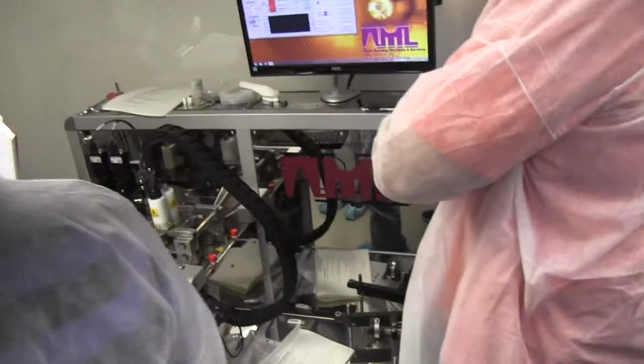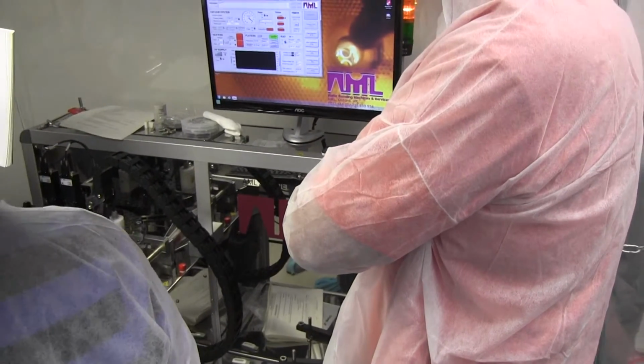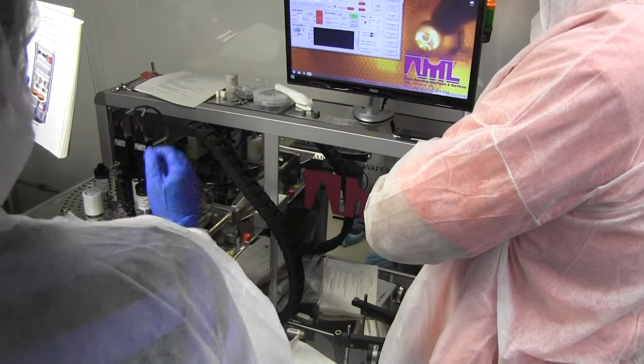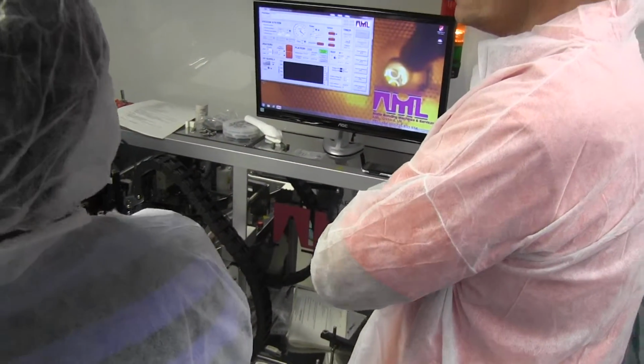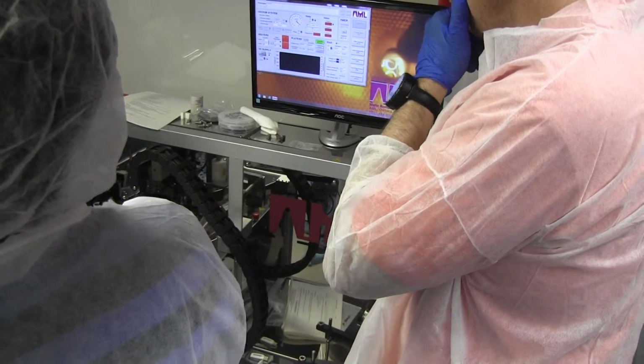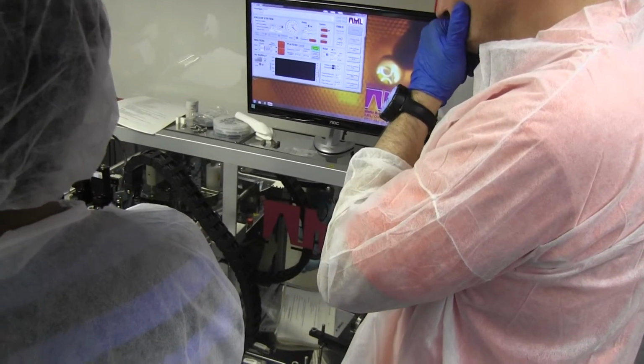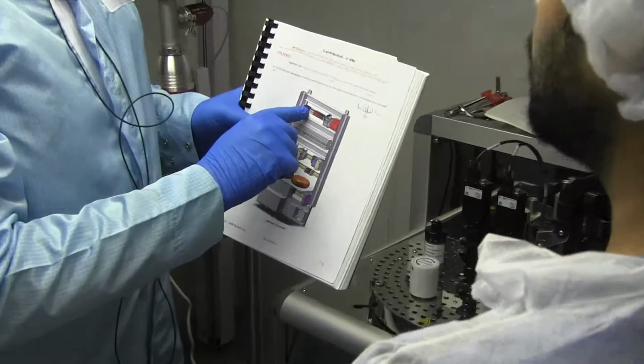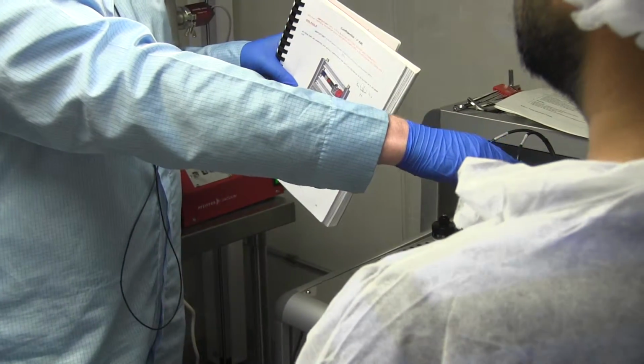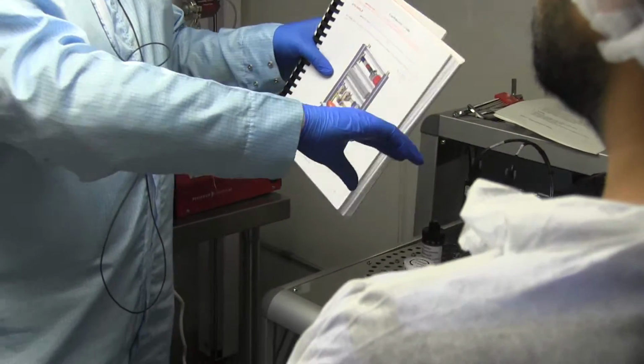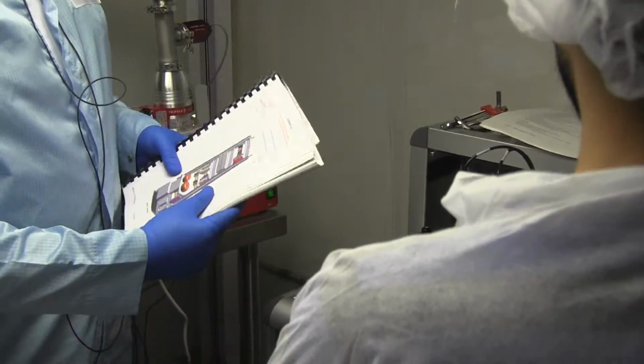If anything trips, you can open this panel. They're accessible through a little slot. That's all you'll be able to see, is what those are. So you can just flick them back on if needs be. And then at the top we have terminal blocks. Blue and white is for mains power. So one mains feed comes into those rails, then that distributes power to everything else inside the machine.